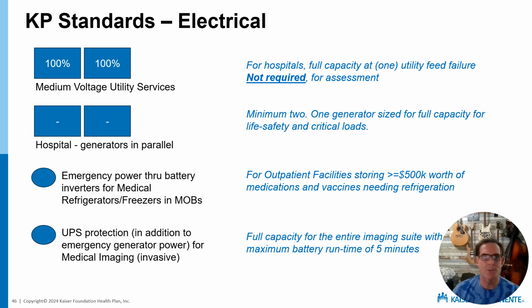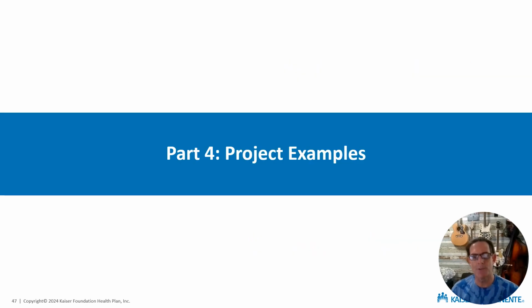For outpatient facilities, for refrigerators with more than $500,000 in pharmaceuticals, we call for battery inverters. You guys actually saw the example behind how we got that together. And then we also require UPS protection for MRI machines, with run times, not long run times, just 5 minutes to save the magnet. I'll show you just a couple of project examples here.